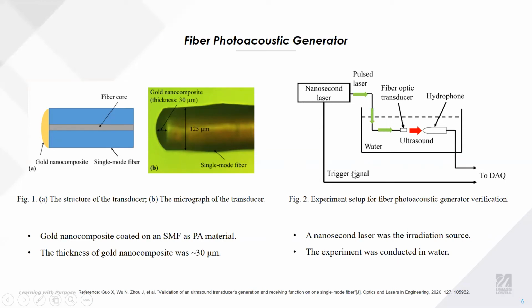Figure 2 shows the experiment setup to verify the generation efficiency of this photoacoustic generator. Again, the light is launched from the nanosecond laser through the fiber and reaches the photoacoustic material at the fiber tip, and this material will absorb the energy and generate an acoustic signal. We use a hydrophone to detect this generated acoustic signal. The whole test is conducted in water.